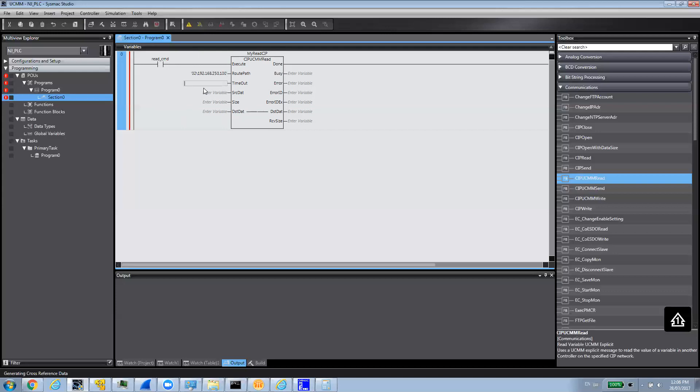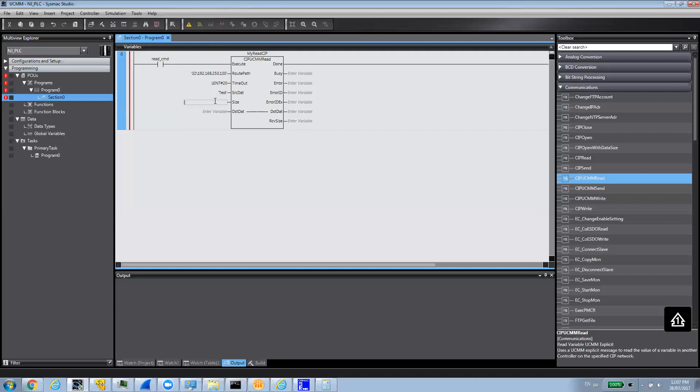I'm just going to put the timeout. I'm going to specify it's 20, which is 2 seconds, because the unit is 0.1 seconds. And then, the source data - that's the variable we created in the Rockwell PLC. So, test. And then, the size, because it's not an array, it's going to be 1. If it was an array, then we could specify the element we want to read of that array.